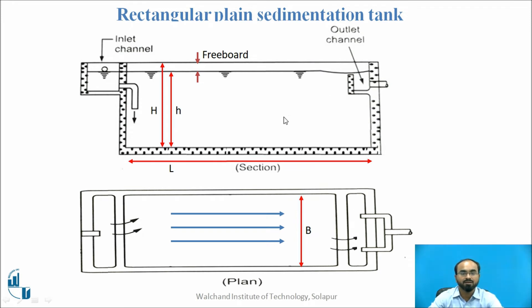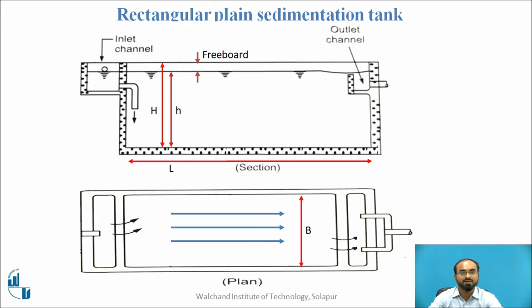Let us have a few diagrams for the plain sedimentation tank. Water is coming from the inlet channel, going into the tank, and passing through length L which has an effective height small h. When we add the freeboard, we get capital H as the total height of the tank. After a particular detention time, water is collected in the outlet channel. Suspended particles settle at the bottom, and a slope of 1 in 100 is given at the bottom so that collected particles can be taken out.